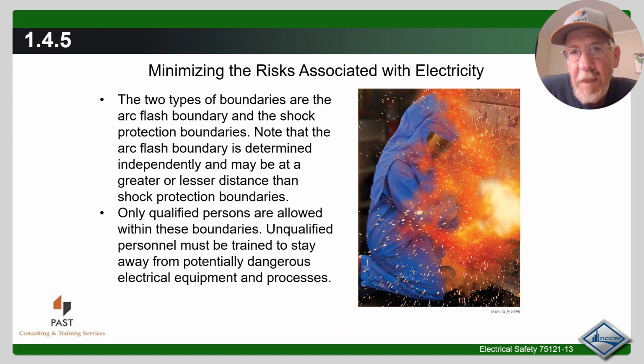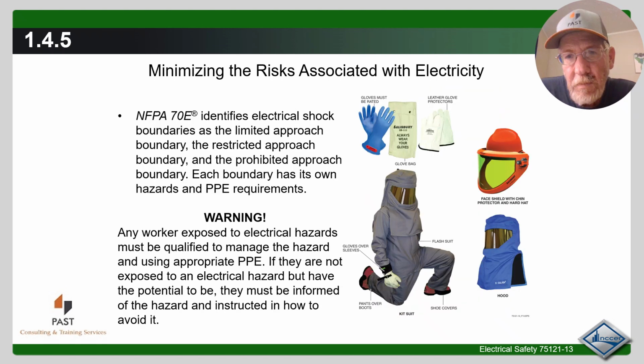The two types of boundaries are the arc flash boundary and the shock protection boundaries. Note that the arc flash boundary is determined independently and may be at a greater or lesser distance than the shock protection boundaries. Only qualified persons are allowed within these boundaries. Unqualified personnel must be trained to stay away from the potentially dangerous electrical equipment and processes. NFPA 70E identifies electrical shock boundaries as the limited approach boundary, the restricted approach boundary, and the prohibited approach boundary. Each boundary has its own hazards and PPE requirements.